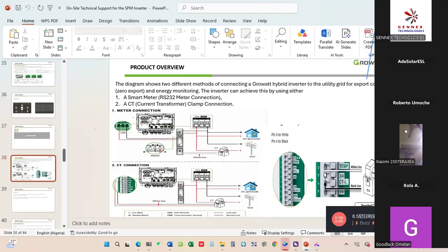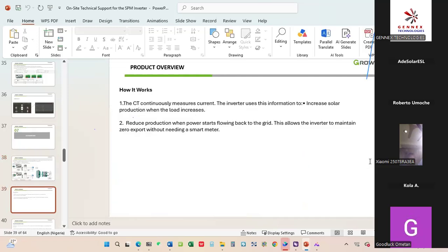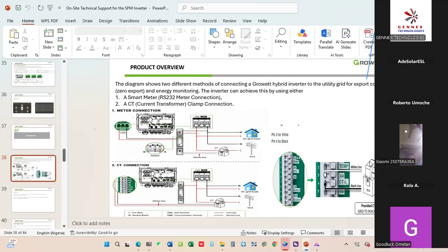So whenever you are installing the CT on your system, always ensure the arrow faces your inverter, and you are not allowed to clamp the live part of the CT. My colleagues have talked about that. I don't know whether you understand. Then you connect the CT to the CT connection terminal. Like you can see, you can connect the white to any of the terminals, the red line to any of the terminals, and the black line to any of the terminals. But make sure the CT is facing your inverter, and the CT should be placed close to your DP. Don't install the CT close to the inverter. Install it close to your DP.